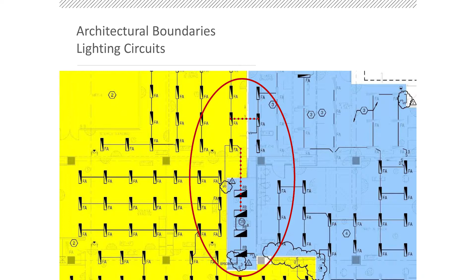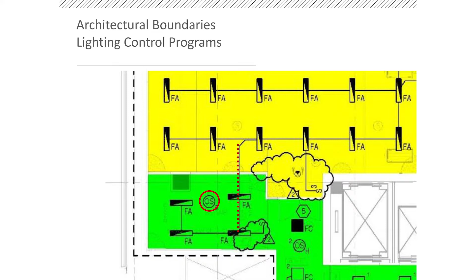This one has more to do with lighting control. We've got an occupancy sensor here in this phase, but it controls the previous phase. This actually happened. So how are we going to get these lights to operate with this occupancy sensor that's not even slated to be installed yet? How are we going to control those lights up until that next installation?